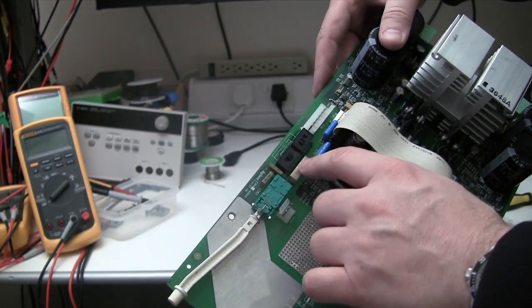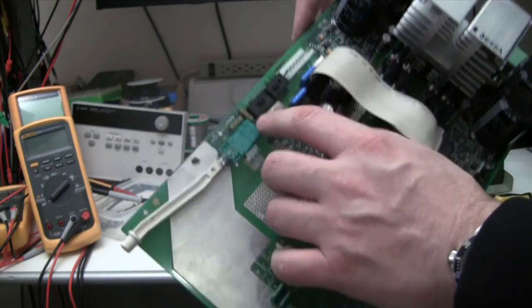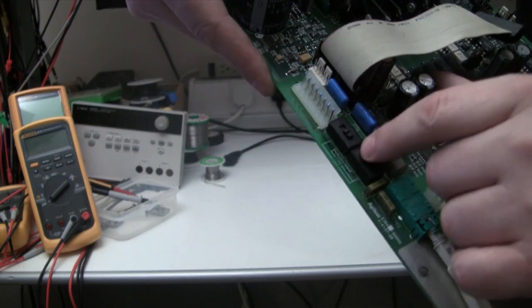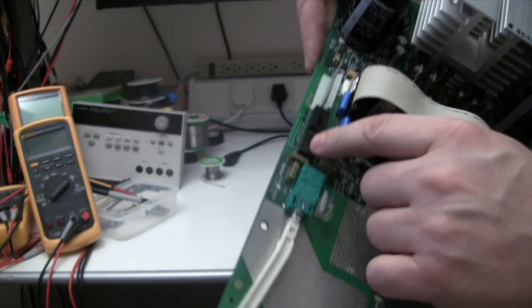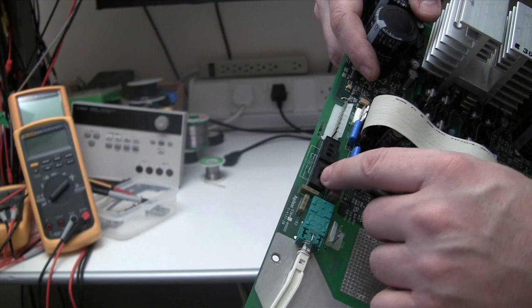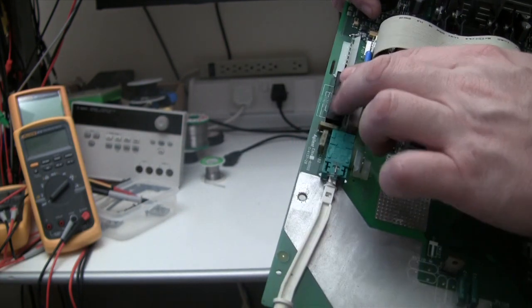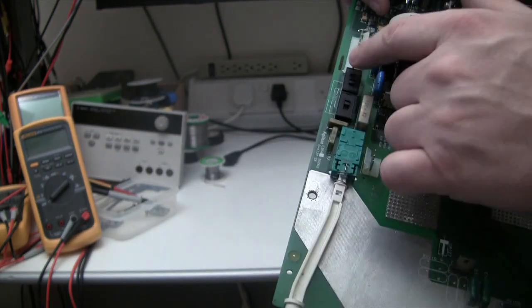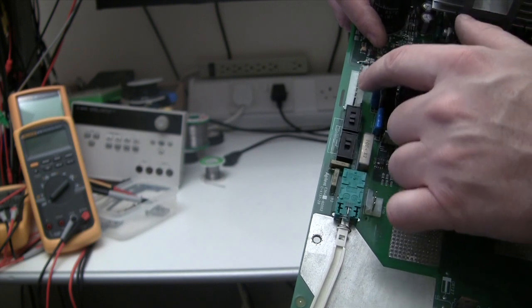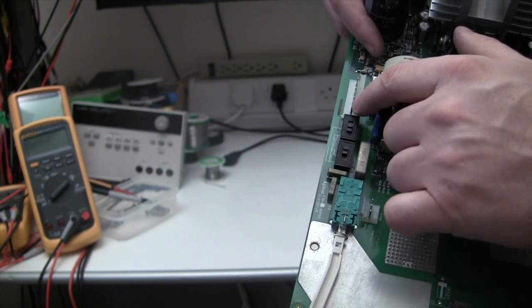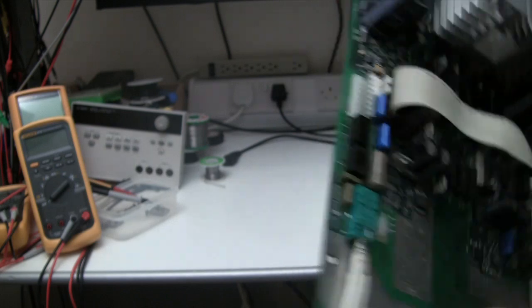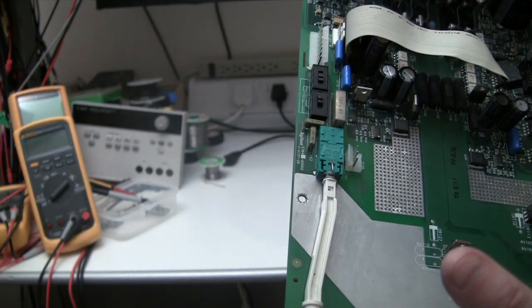Then it goes into these caps, and these two switches here on the board let you set the voltage to the three supported voltages: 100, 115, or 230 volts. This is set for 230 volts, and then this is the connection to the primary side of the transformer.